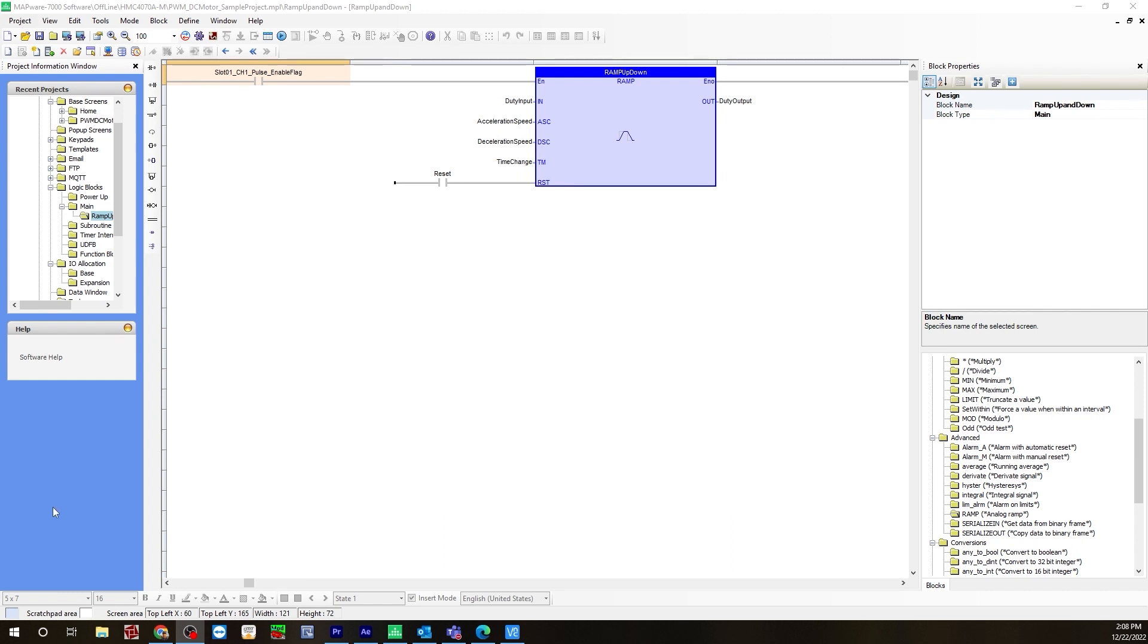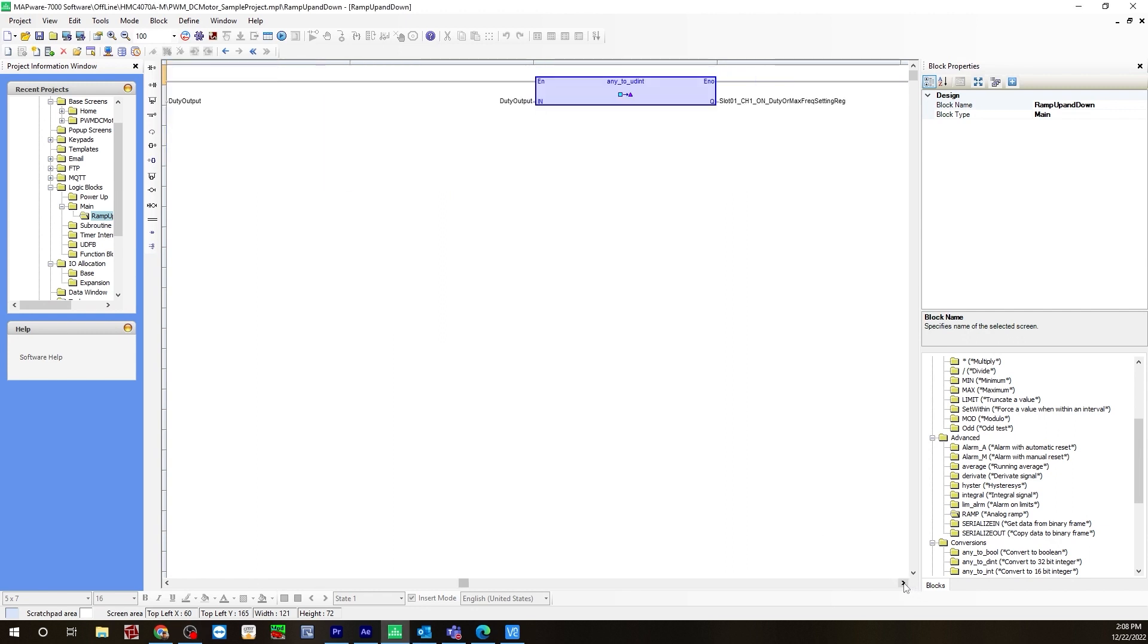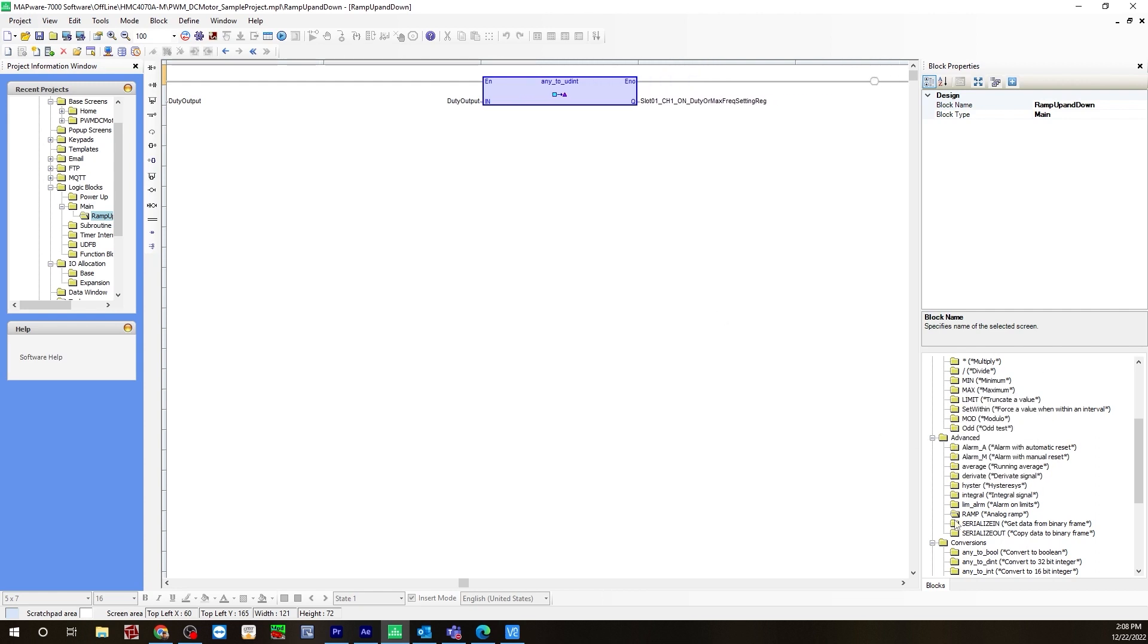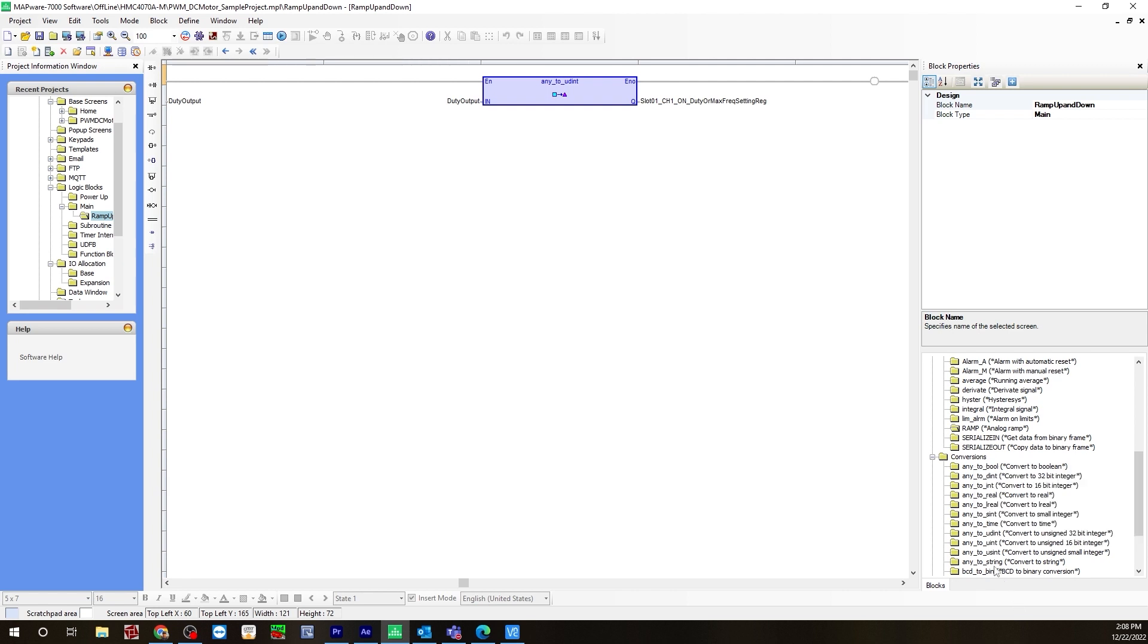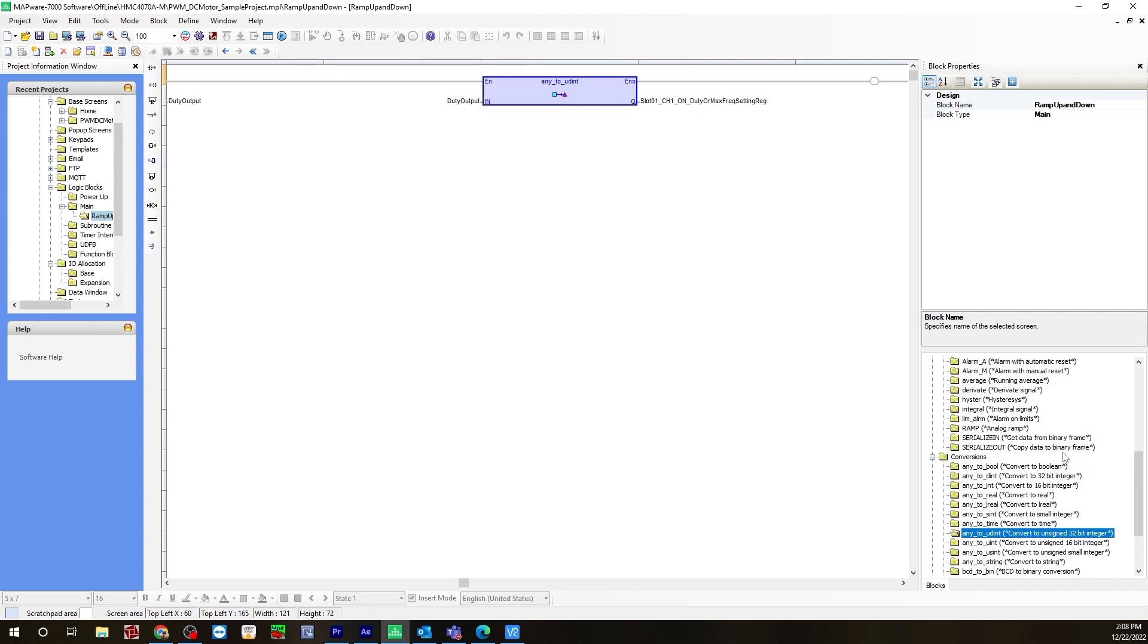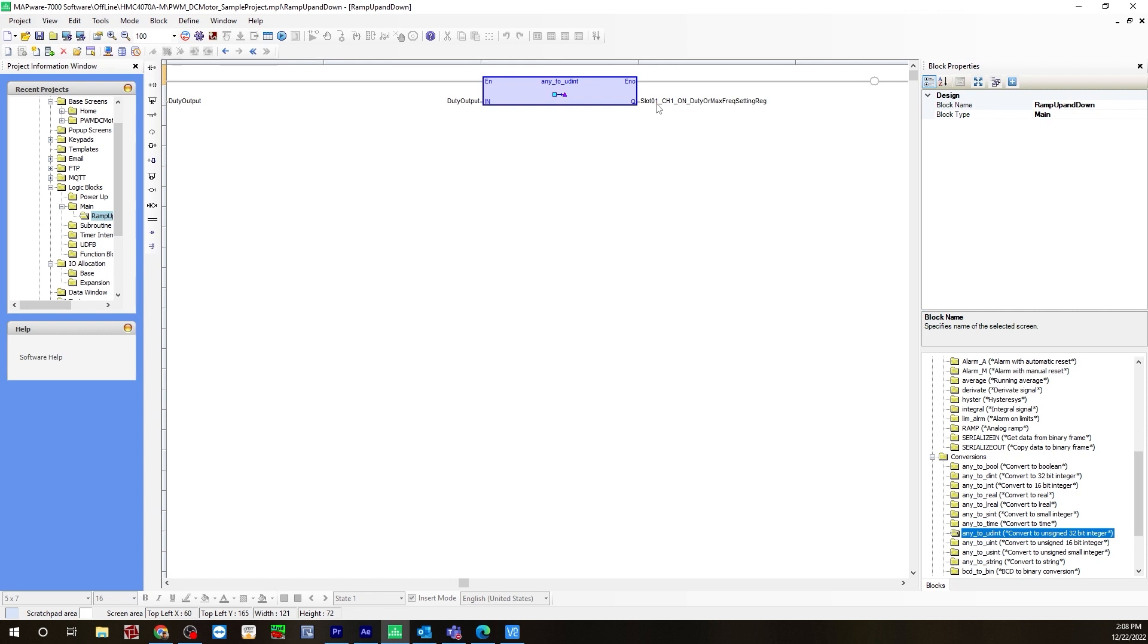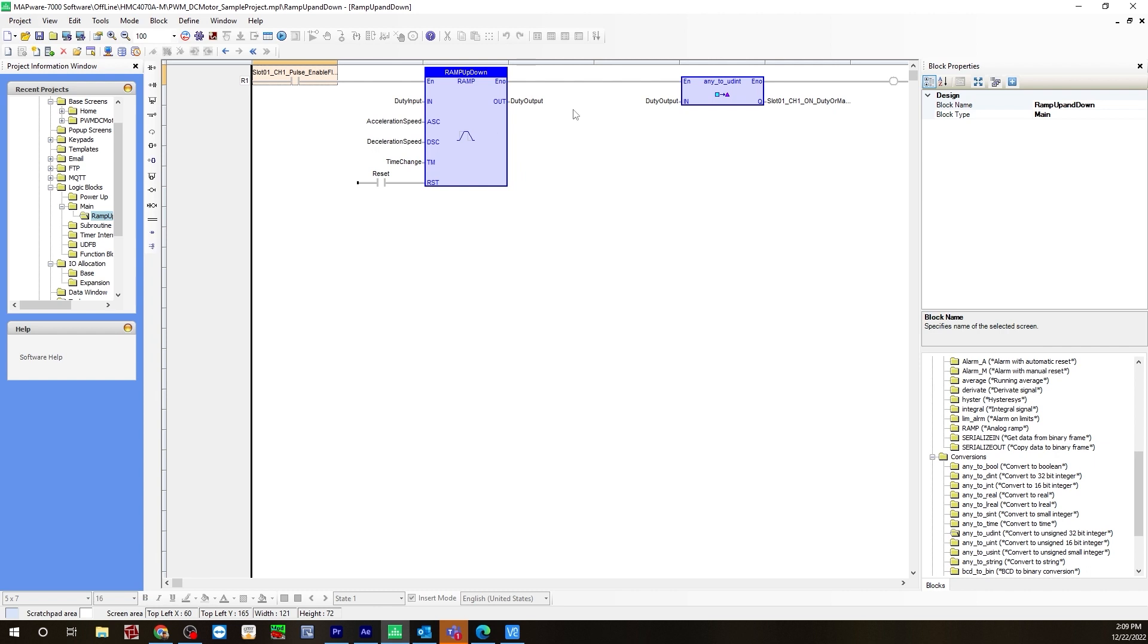The last piece of logic you'll need to include on this is a conversion. That conversion can be found under the conversions folder, and I am using an any_to_udint or any to unsigned double integer convert to unsigned 32-bit integer. You have to convert this duty output to the actual duty cycle register tag, so slot 1, channel 1, on duty, or max frequency setting register. Once you add the three pieces of logic on your rung, this is all you'll need.